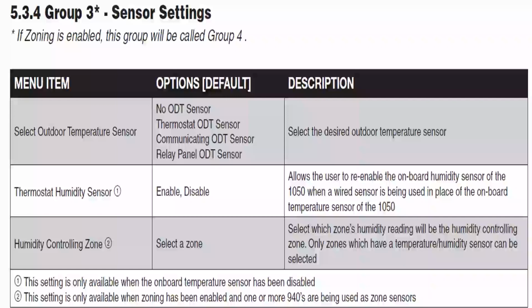It's mostly common to just use the outdoor ambient sensor located in the outdoor unit. Keep in mind, if we do select online weather or internet weather, it's not necessarily at the site. It could be from an airfield or your local school. So it could vary quite a bit from your actual location. And also, during defrost mode, it does not use internet weather. It uses the sensors on board the outdoor unit. So that's a key point right there. For operation, it's always referring to the onboard ambient sensor in the outdoor unit.